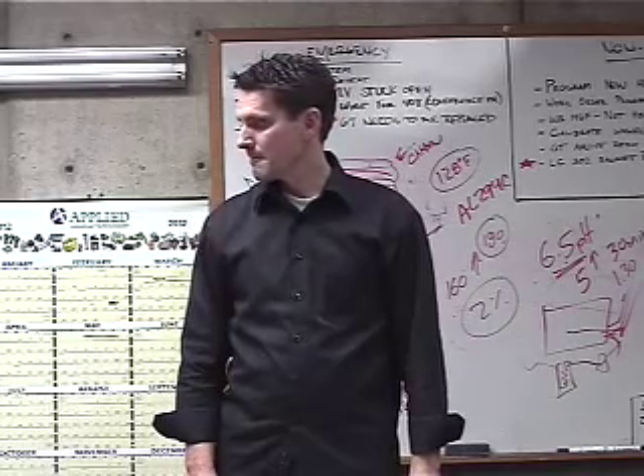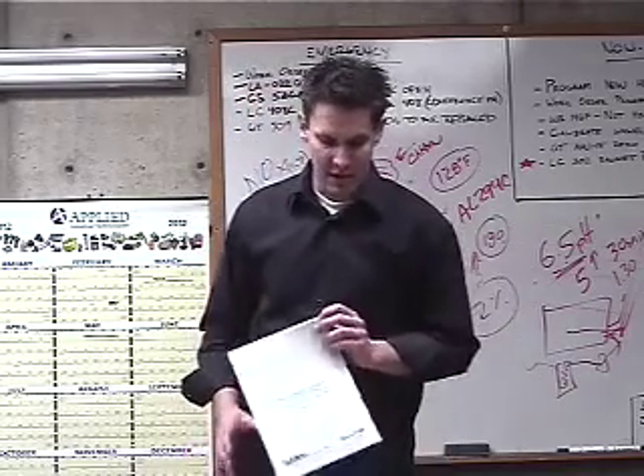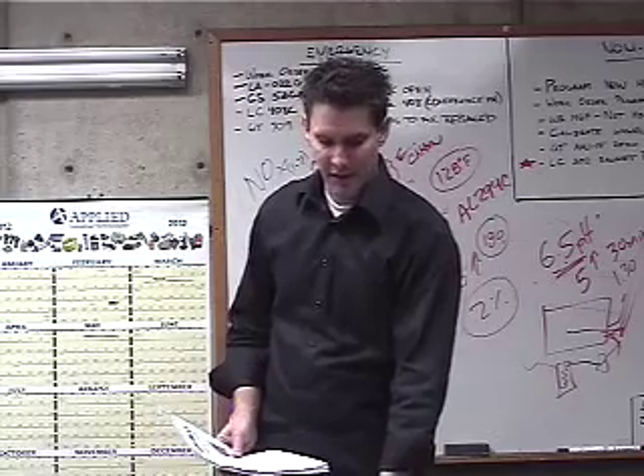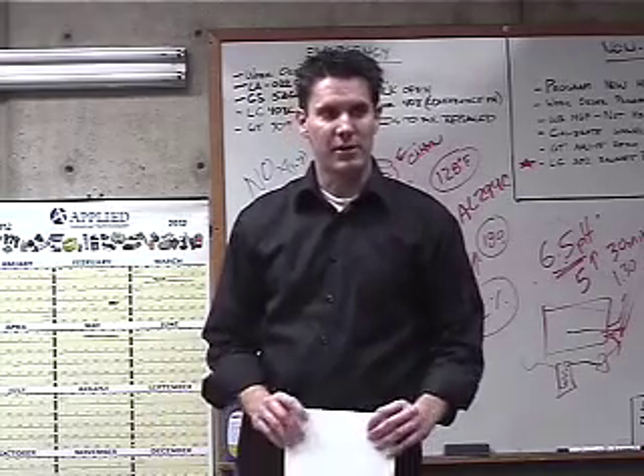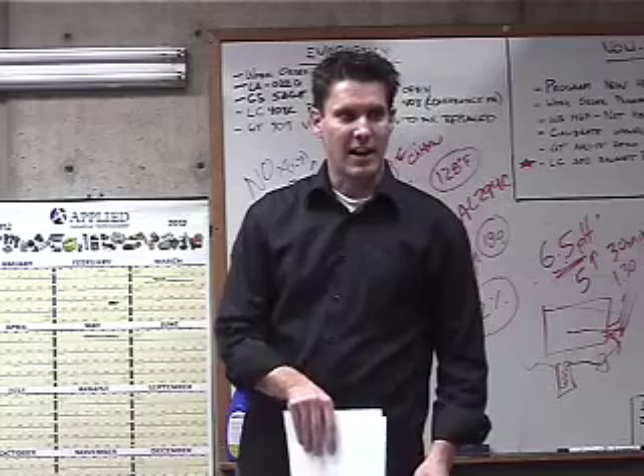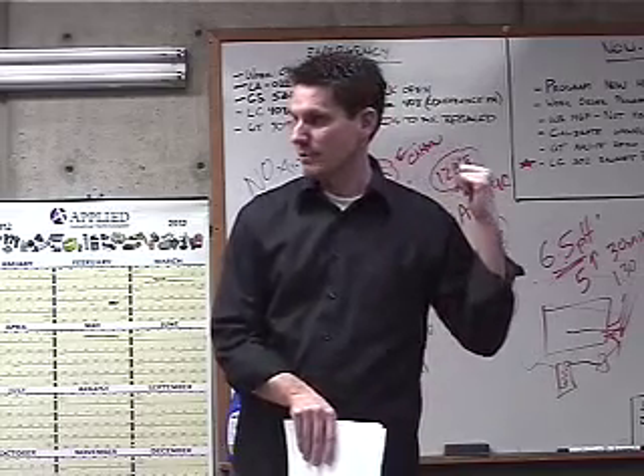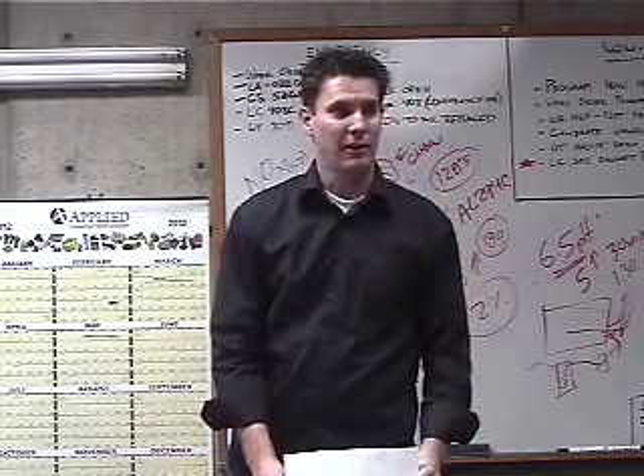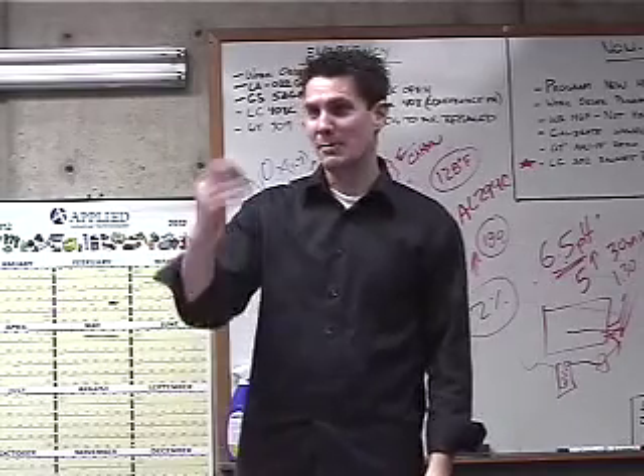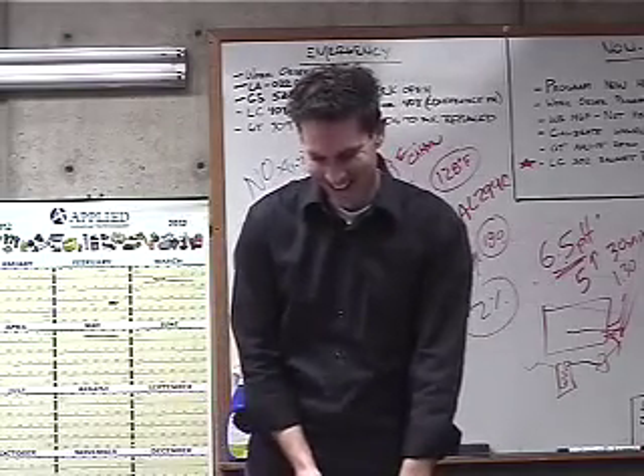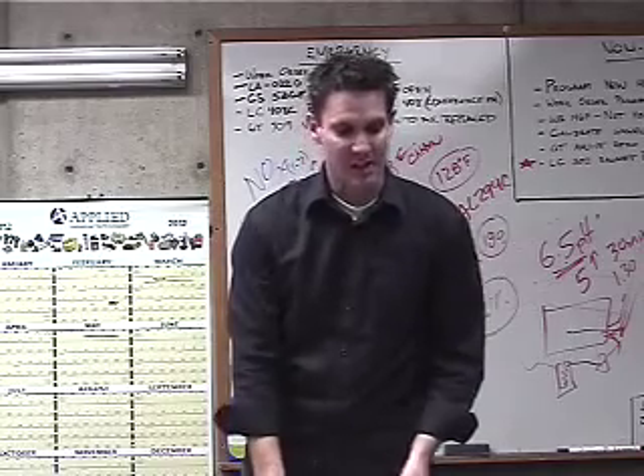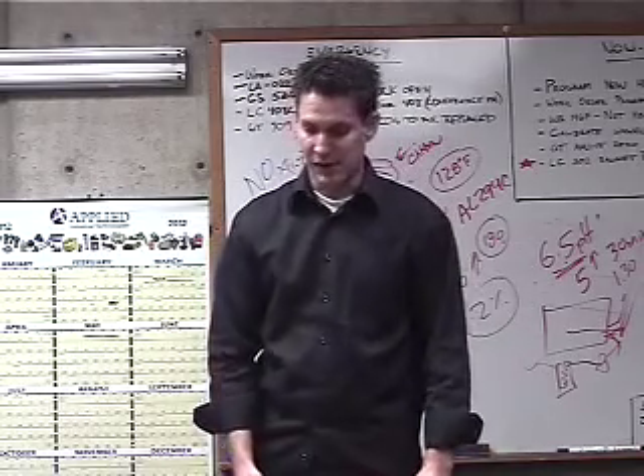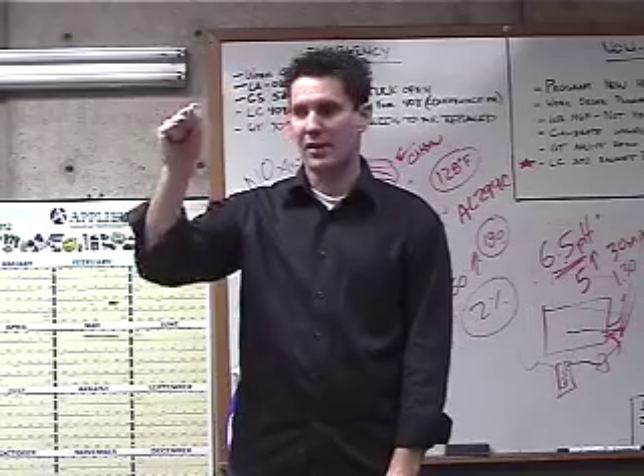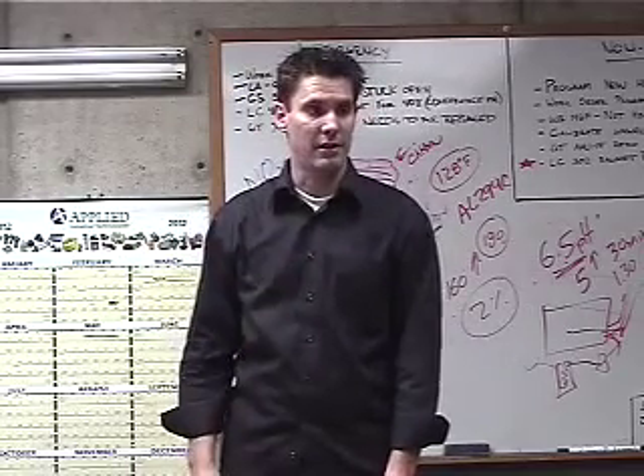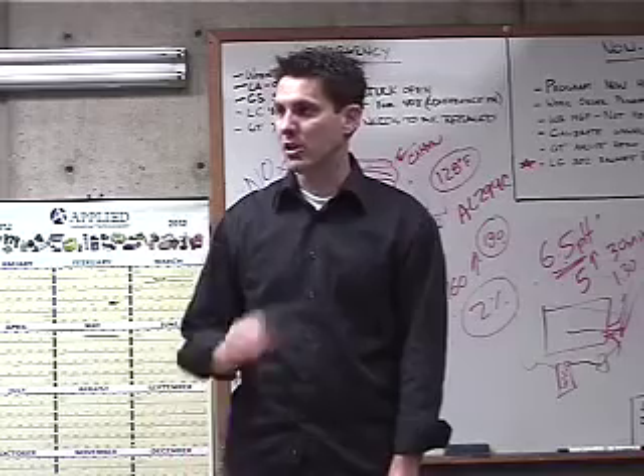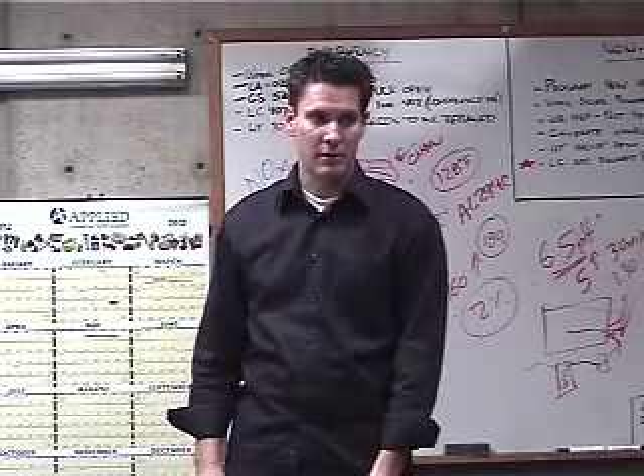Okay. And we still need to come down and do a hydronic balancing class with you guys. You've got all these balancing valves out there. Do you guys do your own balancing, or do you hire it out? How are you going to make sure that a year from now the new science building is still balanced? It will be, because Rocky Mountain did it, right? Brian's our balancer. That's one of the biggest problems we see in these hydronic systems: as soon as somebody uses a balancing valve, which you have manual balancing valves out here, as an isolation valve, your entire system's out of balance. It does that?